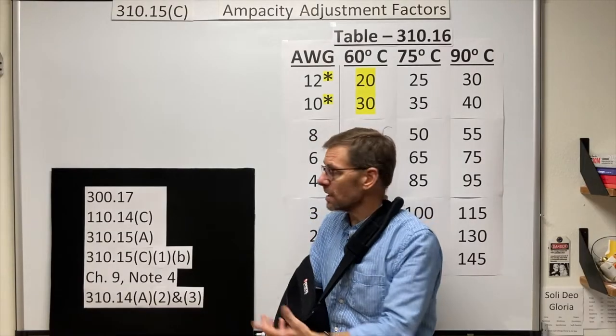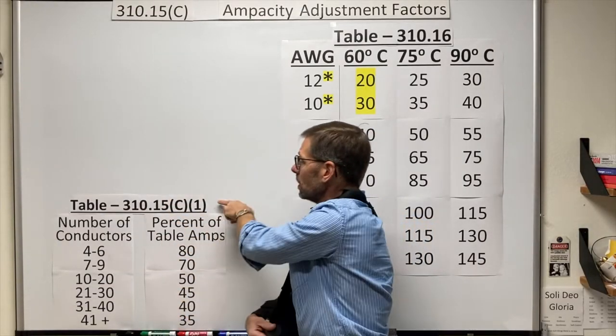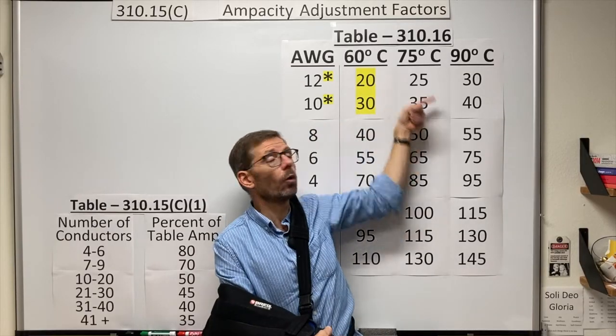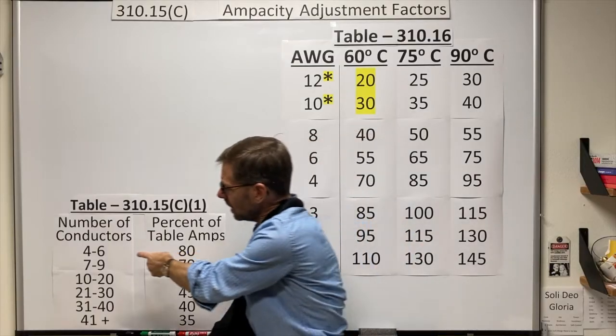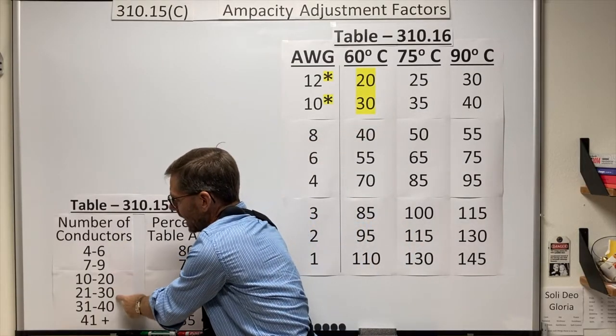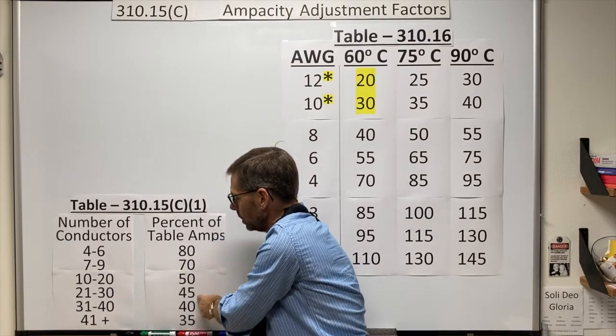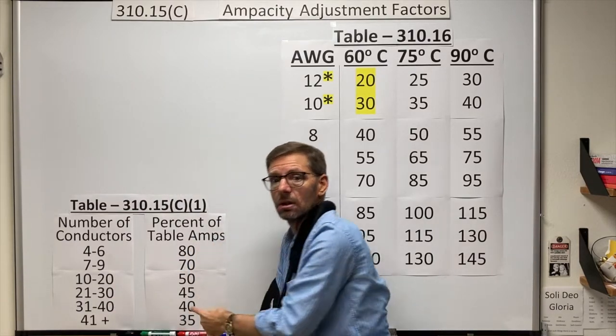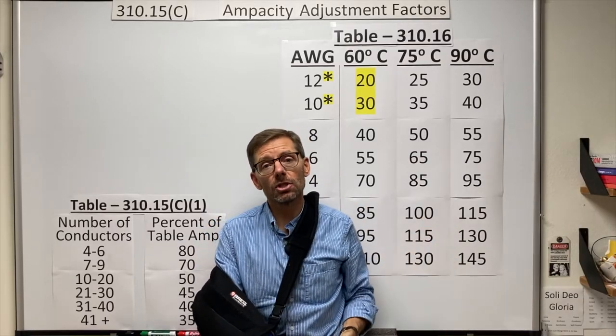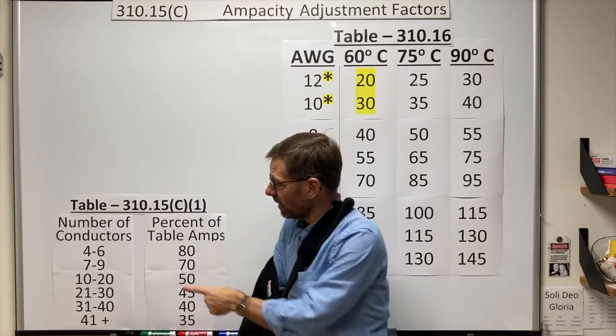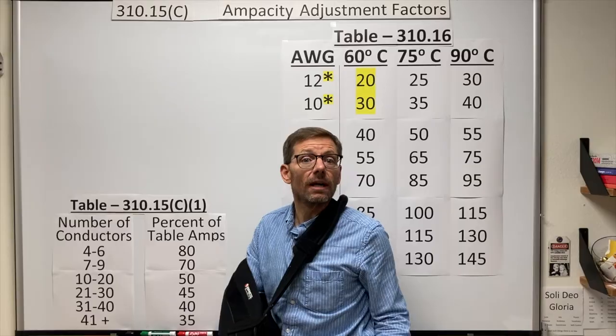So the basic process deals with my ampacity tables and also this table that you'll find a page or two before these tables. As we can tell, the more conductors we have, current carrying conductors, the more we have, the lower the percentage of my original ampacity that I'm allowed to use. So the first step is to find out how many current carrying conductors I'm dealing with.